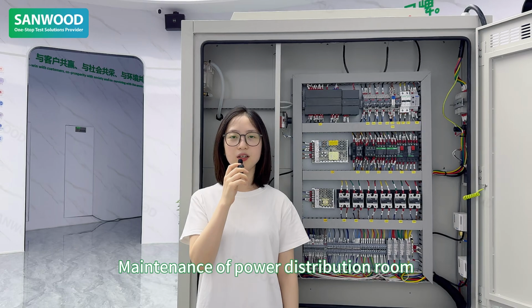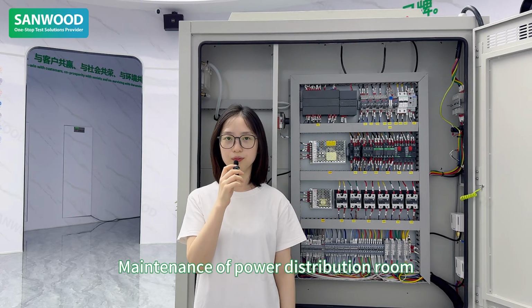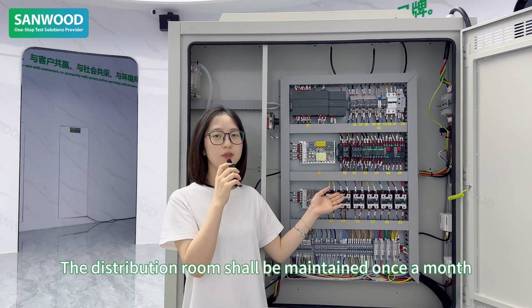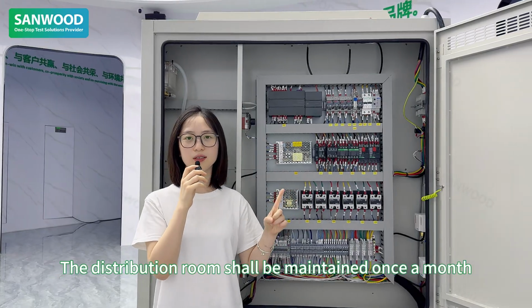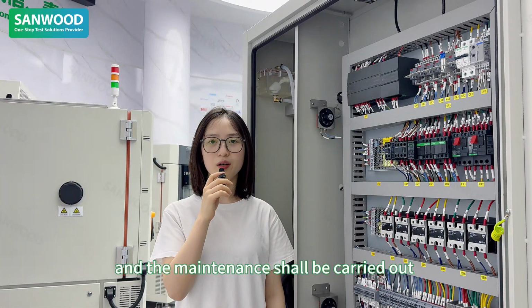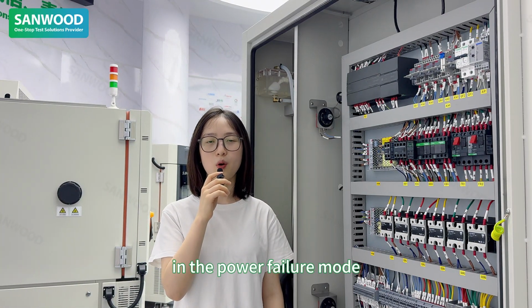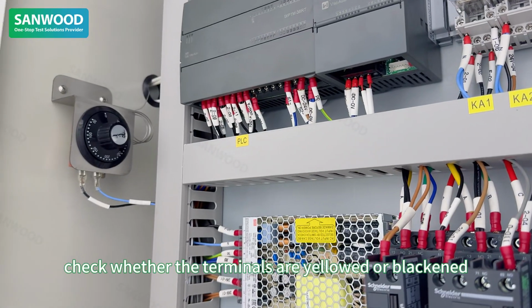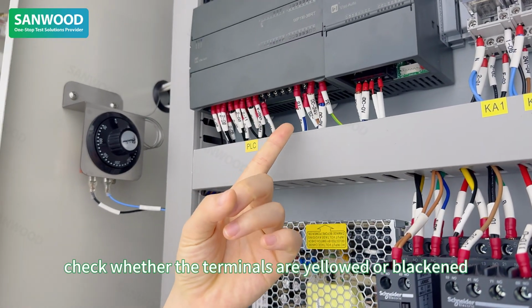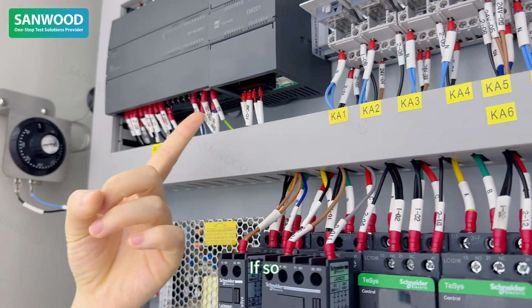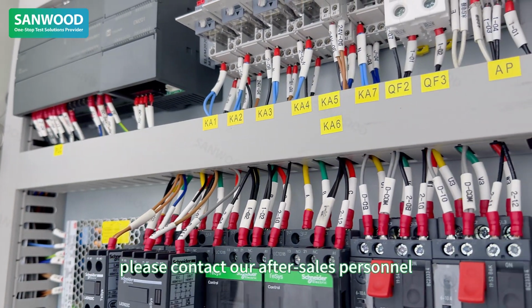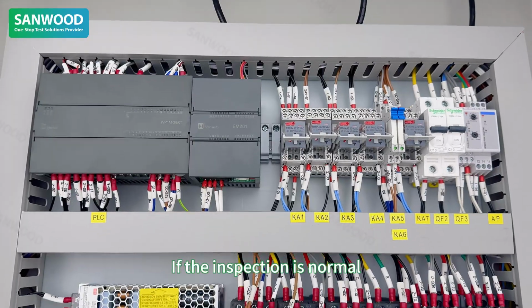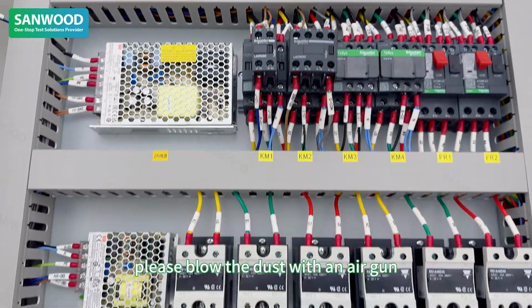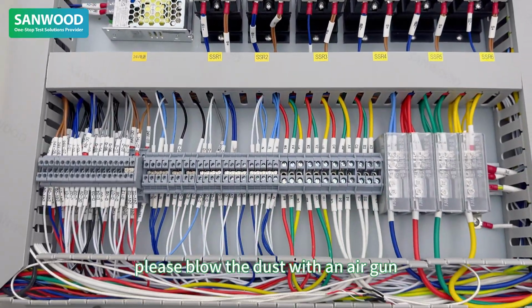First, maintenance of the power distribution room. The power distribution room should be maintained once a month, and the maintenance should be carried out in power failure mode. First of all, check whether the terminals are yellowed or blackened. If so, please contact our after-sales personnel. If the inspection is normal, please blow the dust off with an air gun.